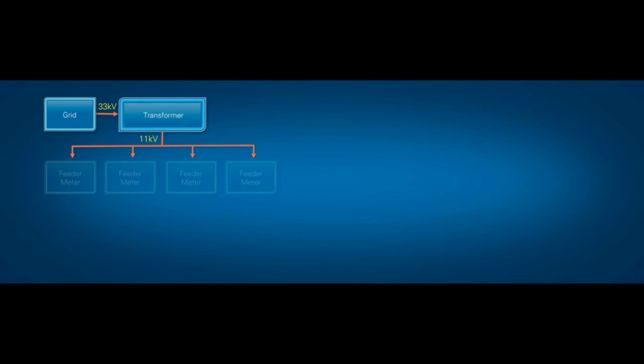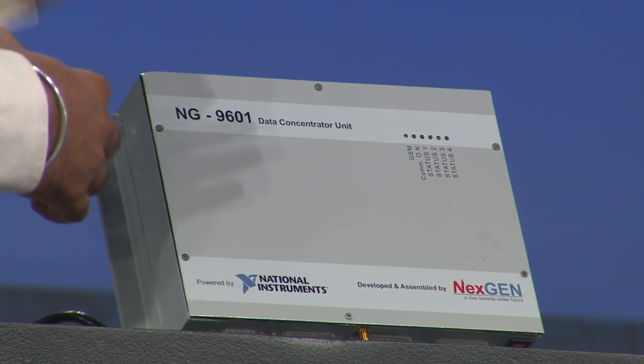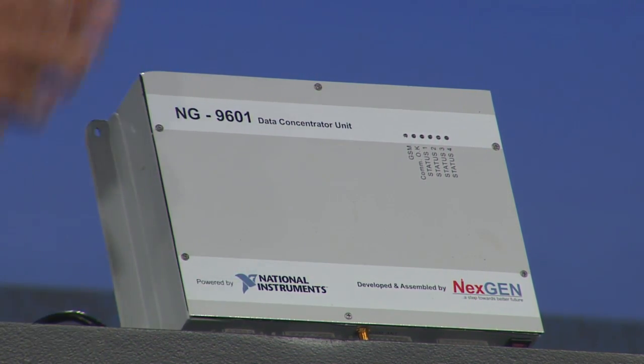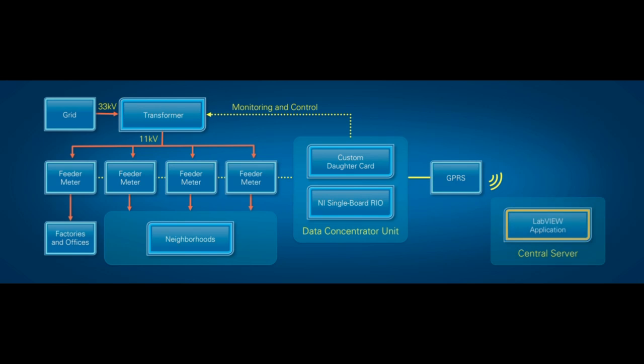The unit is composed of a single-board RIO with a custom daughter card, with digital input and output, RS-485 communication, and a GPRS modem. We are presently deploying 2,820 of these data concentrator units into substations scattered all across the state of Rajasthan.